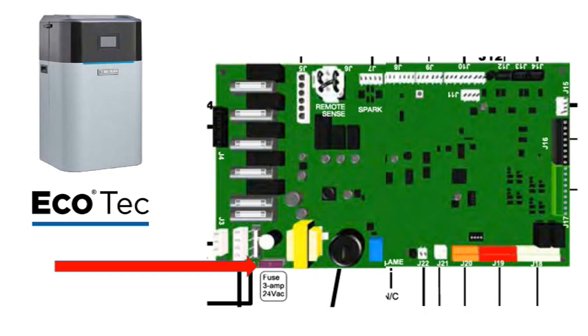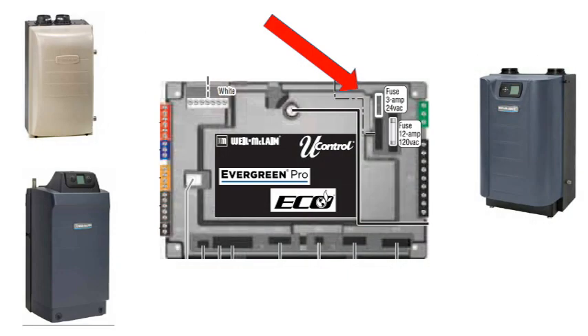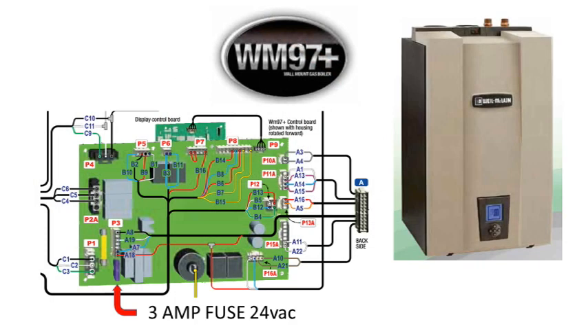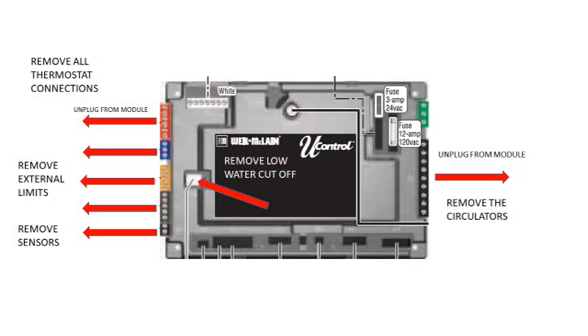So, grab your meter and find out if the fuse is open or closed. If the fuse reads open, let's not just replace the fuse quite yet. Let's see if we can find the reason why the fuse is blown. The easiest and quickest way to find out if the problem is in the boiler or out in the system is to isolate the boiler from all external devices. First, remove all thermostat connections, external limits, external sensors, the low water cutoff, and the circulators. Now, insert another 3 amp fuse, or better yet, a 3 amp circuit breaker, and energize the boiler.